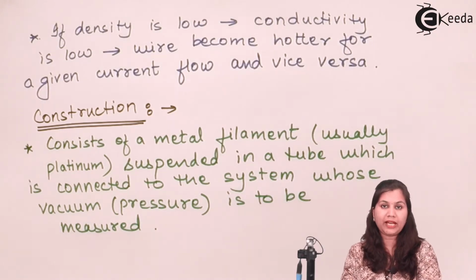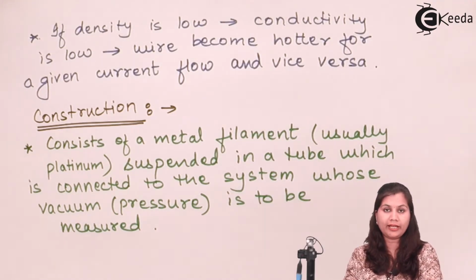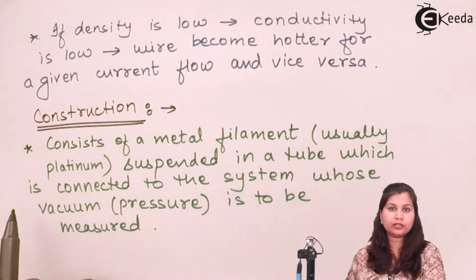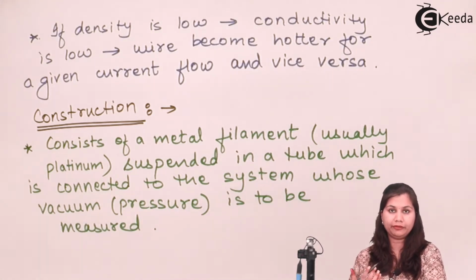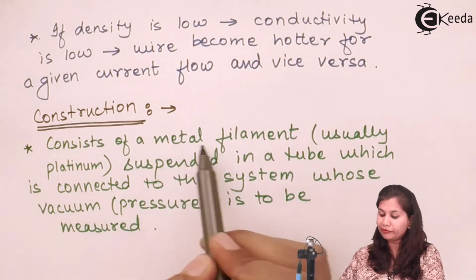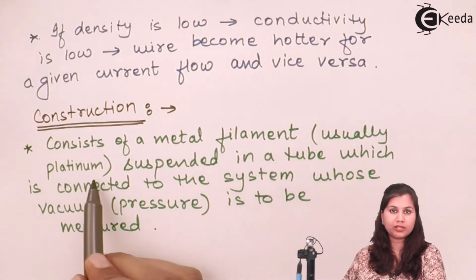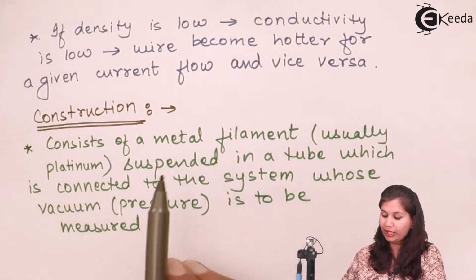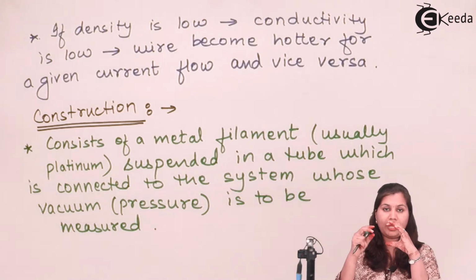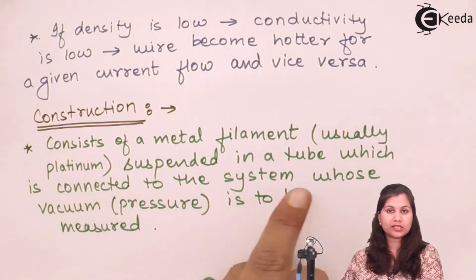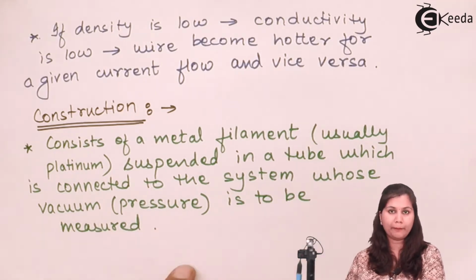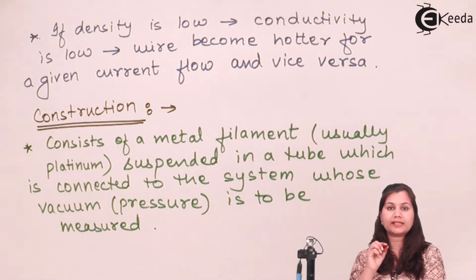So in the basic principle, we have studied that we were having a conducting wire, and the conductivity of that wire is changing. Okay. So in the construction, the Pirani gauges, they consist of a metal filament or the conducting wire. This metal filament is made up of, usually platinum is used as the metal. So this filament is suspended in a tube, means this filament is kept in a tube which is connected to the system whose vacuum or pressure we want to measure. So here in the Pirani gauge, we will be having a tube in which the platinum filament will be there, and this tube is connected with the system whose pressure we want to measure.